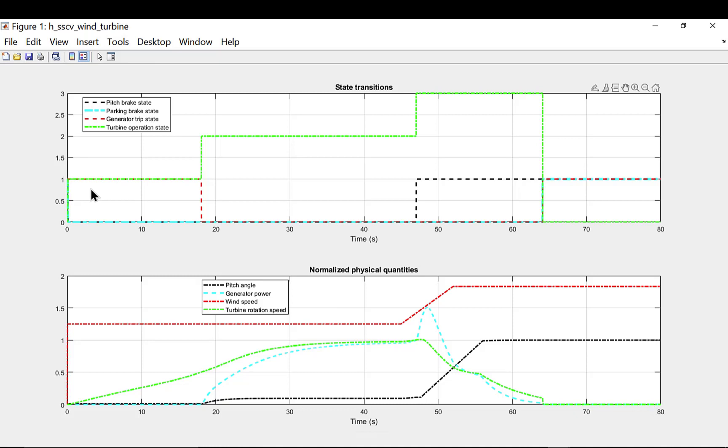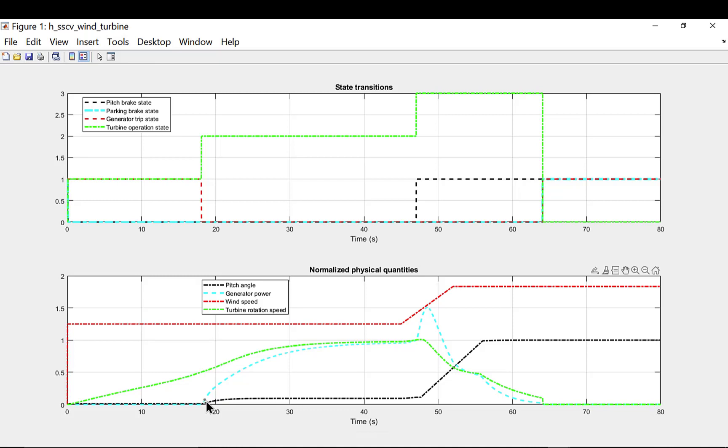Turbine stays in park brake mode for initial 0.1 second. Once wind speed goes above the cut-in wind speed, rotor starts to accelerate. It goes up to cut-in rotation speed and then generation mode gets active. Generator gets connected with the grid, power generation starts.